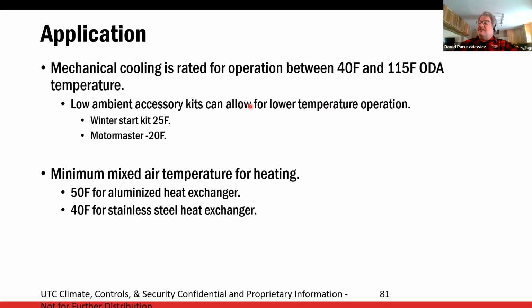So, low ambient accessory kits for rooftop units. A rooftop unit out of the box is designed to run down to 40 degrees Fahrenheit. If you do nothing to it, it will run down to about 40 outside. Now the grow rooms will require air conditioning year round, so we need to look at the proper low ambient accessories. The Motor Master here is a condenser fan speed control, really simple to put in, and it runs on condenser temperature, not pressure. But you also need this winter start kit. We'll see this a little further on.